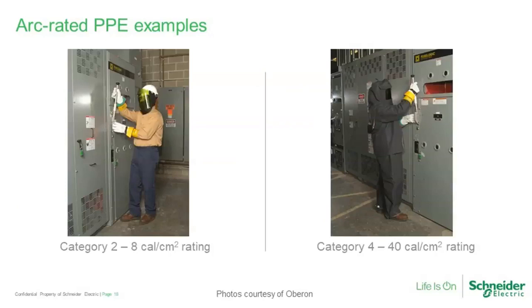Just real quickly, arc-rated PPE examples. You can see here why I'm making the distinction between the quote-unquote light-duty and heavy-duty PPE. On the left-hand side, 8 calorie per centimeter squared rating. The worker's there in a face shield, with a treated shirt and pants to achieve that rating. On the right-hand side, where you want a little bit more protection, 40 calories per centimeter squared. Again, the full flash suit with the hood, with the specially designed face shield, and you can see quite a bit higher level of protection is required when we move up in those energy levels.